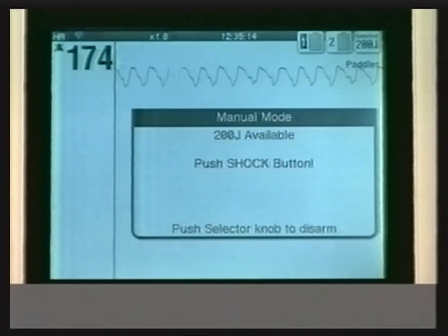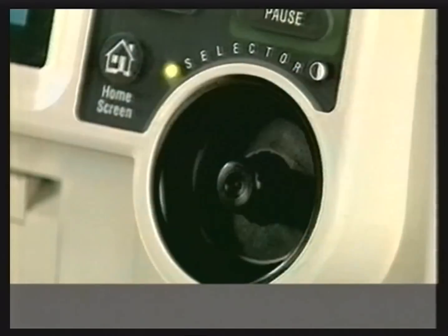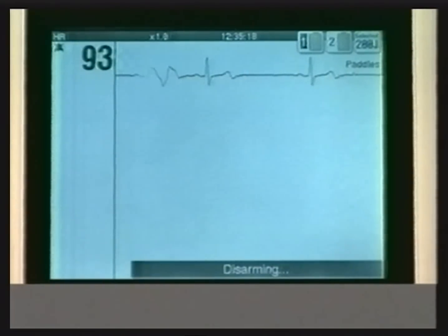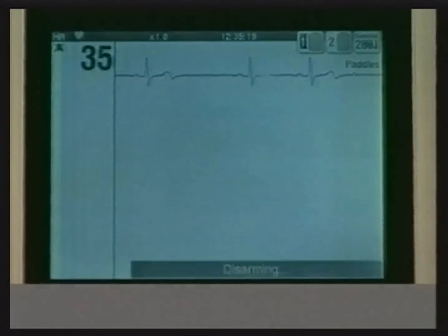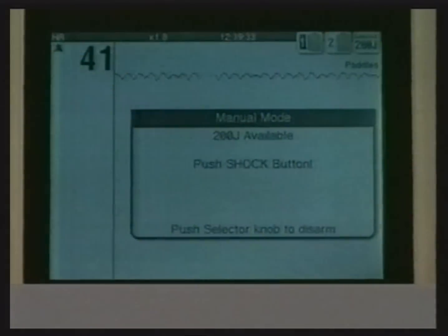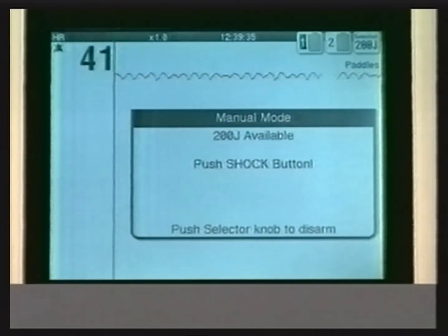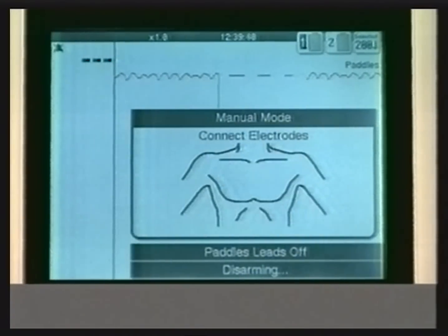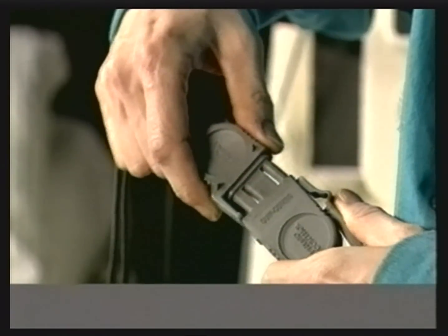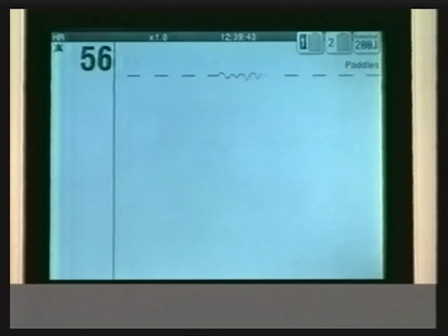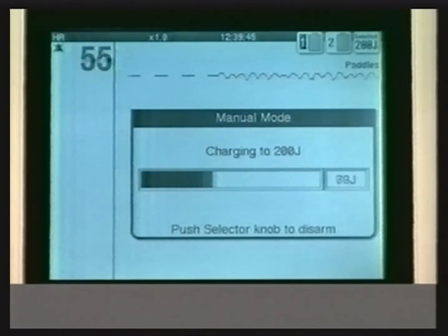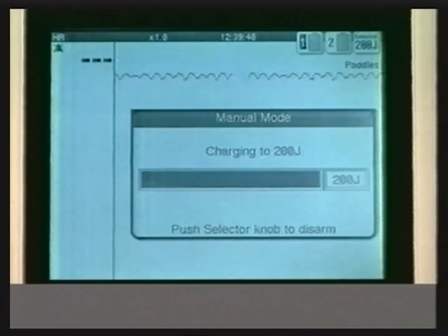You can remove an unwanted charge at any time by pressing the selector. The energy is removed internally. The charged defibrillator also disarms automatically if shock is not pressed within 60 seconds, if the electrodes or cable become detached, or if energy select is pressed. Press charge again to recharge the defibrillator.